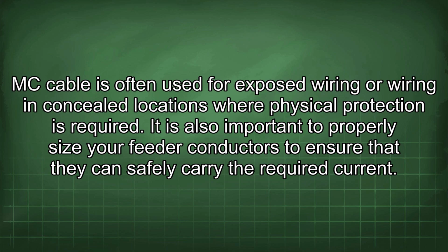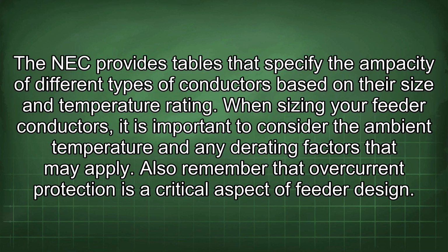It is also important to properly size your feeder conductors to ensure that they can safely carry the required current. The NEC provides tables that specify the ampacity of different types of conductors based on their size and temperature rating. When sizing your feeder conductors, it is important to consider the ambient temperature and any derating factors that may apply.